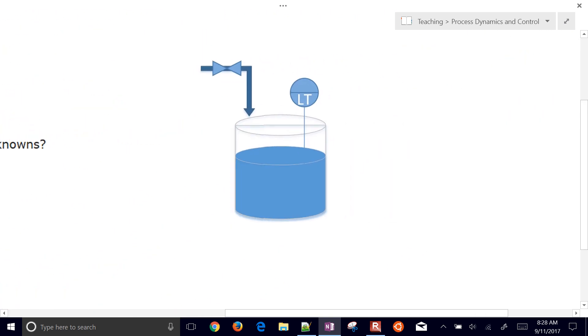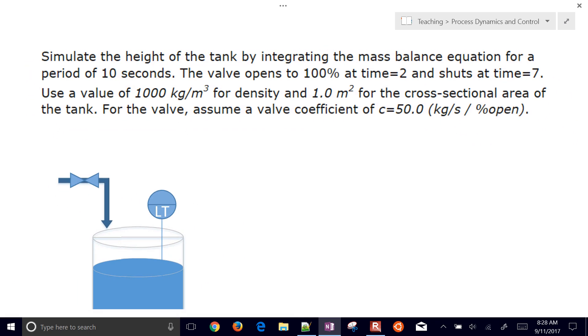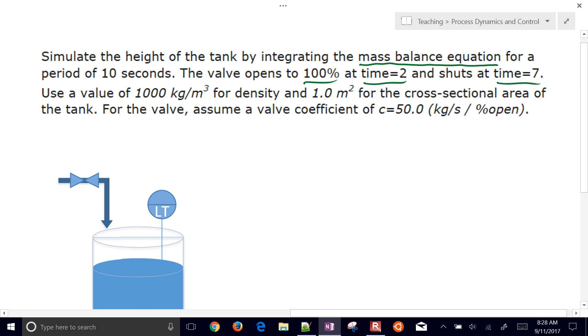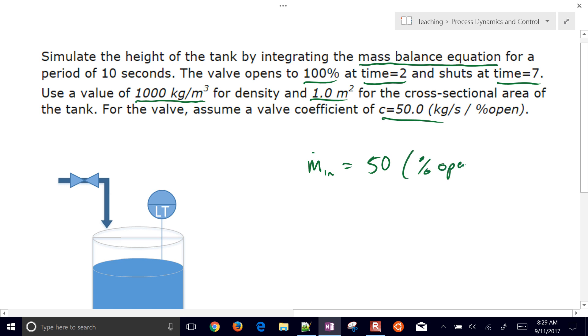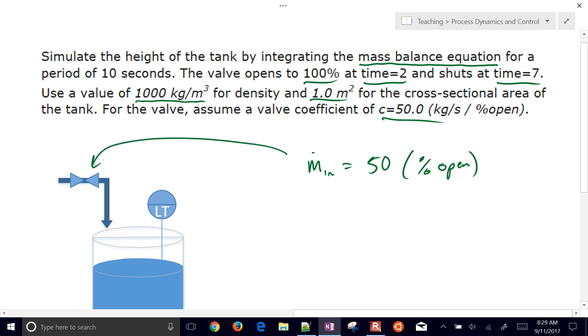Let's do this for an example problem — simulating the height of a tank by integrating the mass balance equation over 10 seconds, where a valve opens to 100% at time equals 2 and shuts at time equals 7. We'll use a density of 1,000 kg/m³, a cross-sectional area of 1 m², and a valve coefficient C equals 50, so the inlet flow equals 50 times the percent open. At 100% open that's 5,000 kg/s.